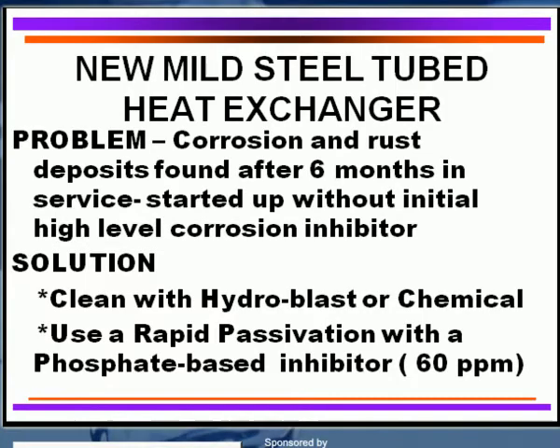Let's go into the next area, which I believe is probably one of the more important areas, and that is the heat exchangers themselves. If you're in a refinery, chemical plant, or you use mild steel tube heat exchangers, we have seen where corrosion and rust deposits have occurred within a very short period of time when a new one has been started up.